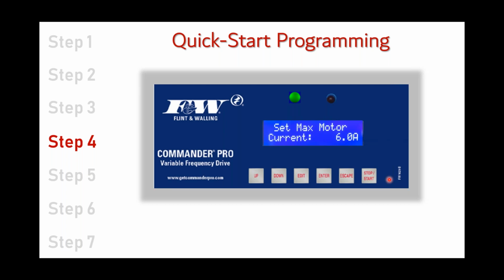When I look at this one right now on your screen, it says 6.0 as the max motor amps. That's probably in line with a 1.5 horse, 3-phase motor. If it were a 2 horsepower, it'd be perhaps 8.2 or 8.3, and a 3 horsepower would be 10.3, 10.2. If you wanted to change the horsepower on this, you would hit the edit button. Then using your up and down, if you're going from 1.5 horse to 2, so you need to raise that max amps from 6 to say 8.2 or whatever the rating is on that motor, you'll use your up button to get to that point and then hit enter to save it. Voila, you just changed the horsepower of the motor that the drive is going to be expected to operate. So again, this is real easy programming up front here.